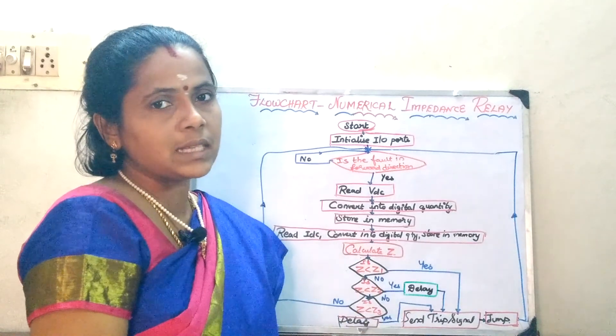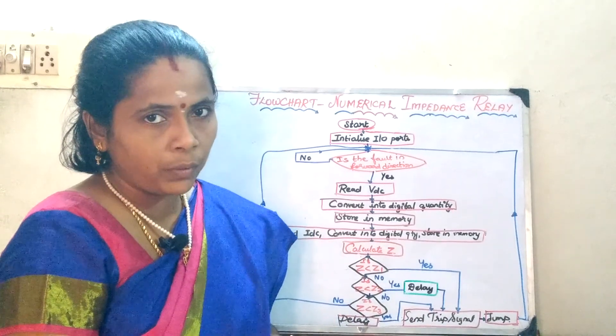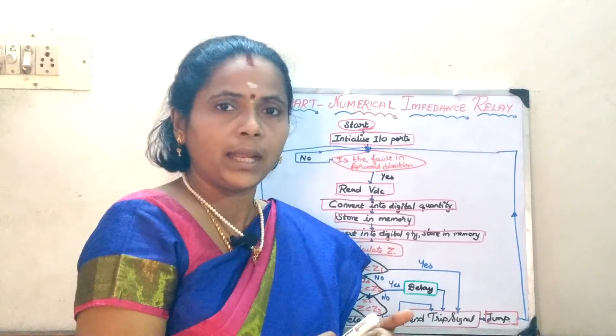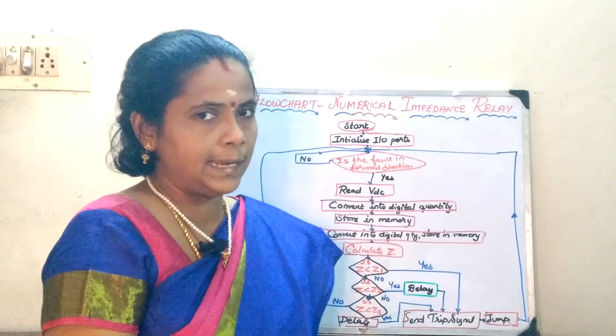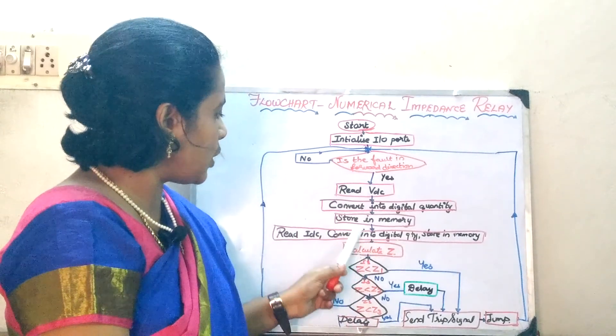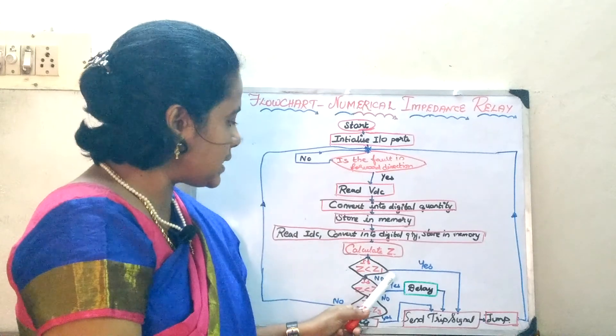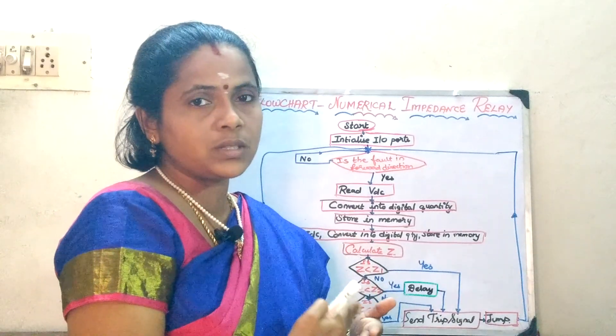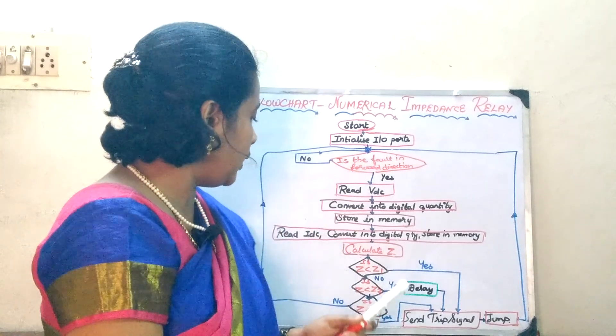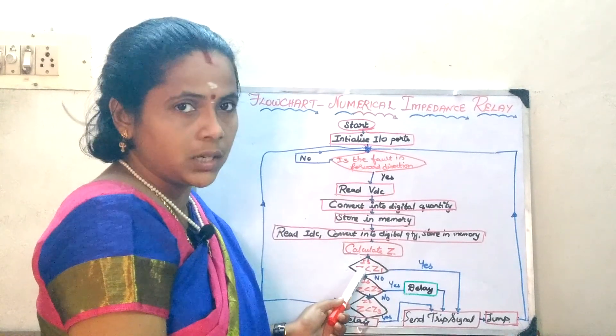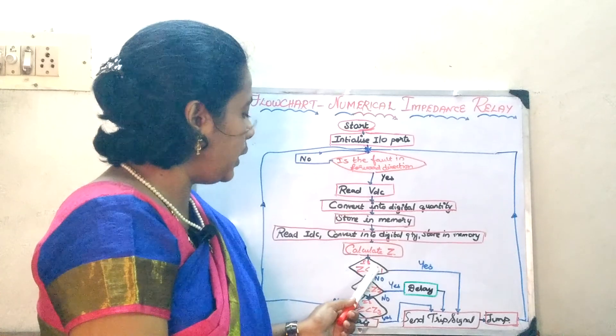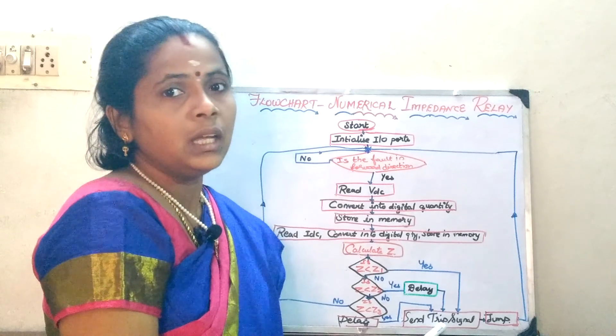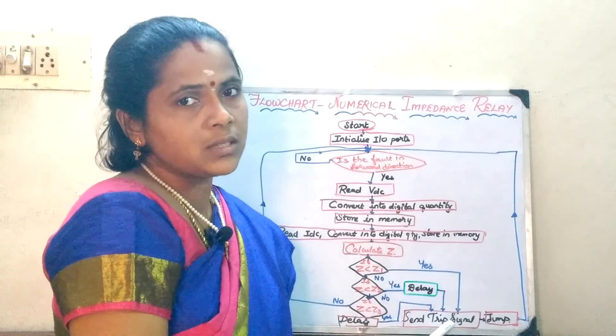This impedance relay, as we saw in the last class, depends on three-zone protection. The first zone protection is the primary protection which will act immediately or instantaneously without any delay. The V/I ratio is taken as Z, and Z1, Z2, Z3 represent the impedance for the first, second, and third zone protection. If the impedance is less than Z1, immediately without any delay you give the signal to trip the circuit breaker.